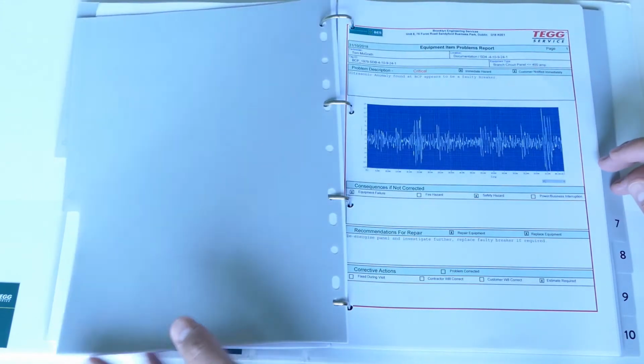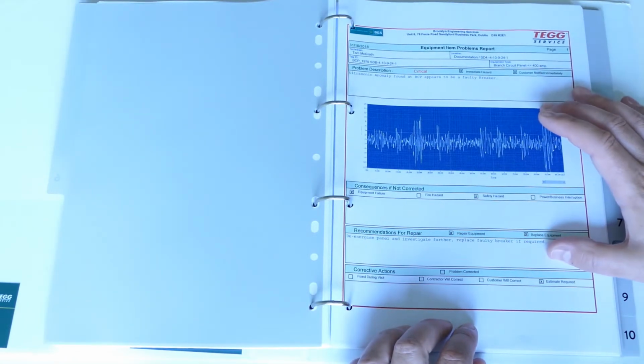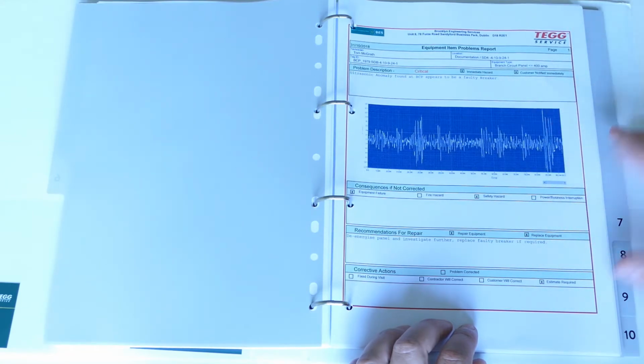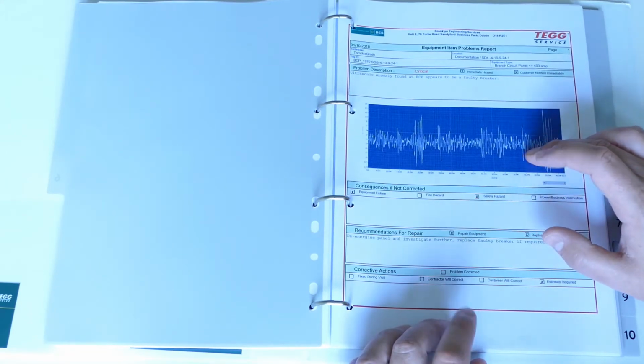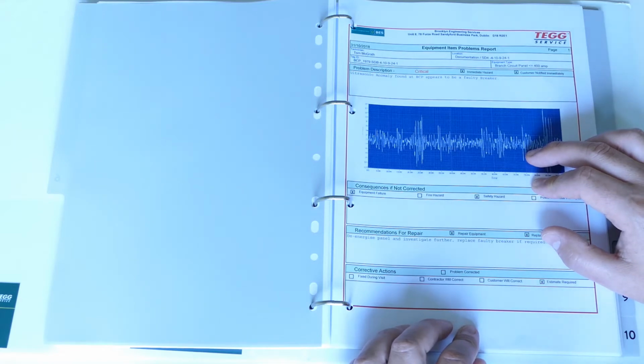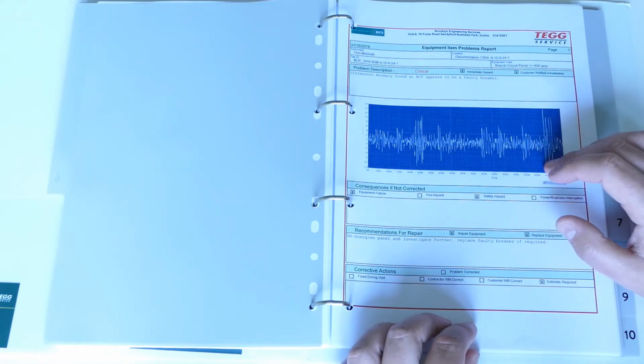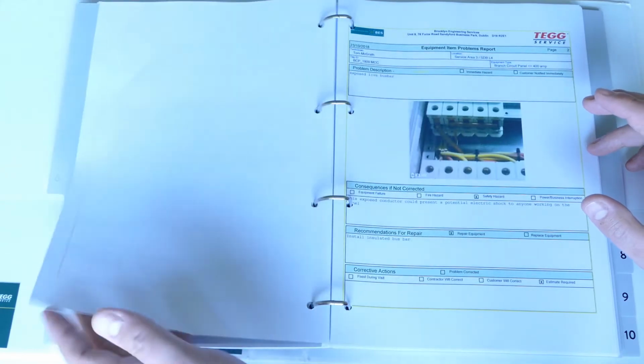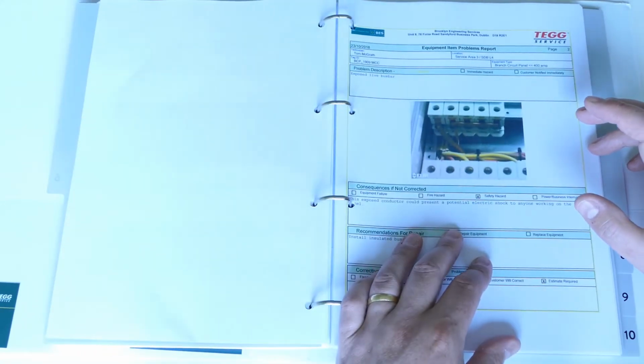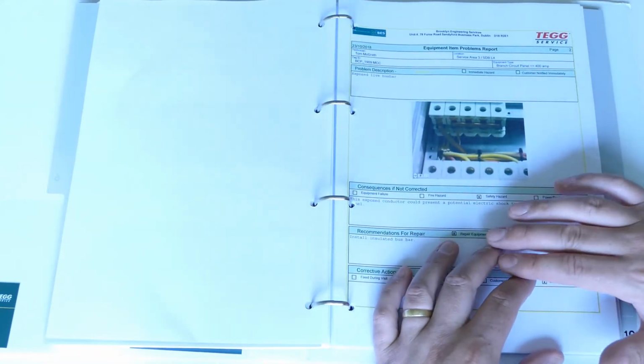Moving into section 6, we have the visual issues. We begin with any ultrasonic issues if there are any. This example is an arcing breaker that was picked up on a small branch panel by the technicians last year using the ultrasonic probe. Then into the visual section, so everything from exposed copper to live bus bar, missing trunking, redundant cables, whatever it might be, is detailed with a recommendation for repair.